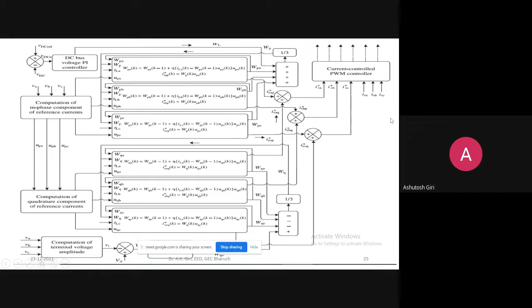Then finally we get phase A active and phase A reactive from this, and they are added to get the reference current of phase A. Similarly reference current for phase B and phase C, and then actual current is sensed, and finally they are compared and fed as a modulating signal to the PWM controller. It may be a hysteresis controller also, and finally you get the current pulses, or gate pulses, for the inverter circuit. The remaining operation, whatever is set, accordingly the inverter will work and control the microgrid operation.